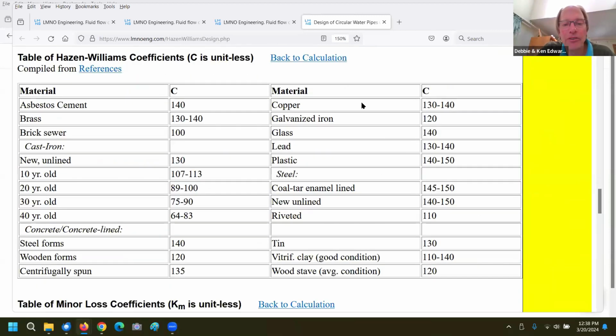Come down here, for instance, copper pipe, your C coefficient's like 130 to 140. Galvanized iron's a little lower. Lower number means rougher. Plastic, 140 to 150, pretty smooth. These are for materials that are newly put in a system. Over time, especially in the water industry, you're going to get calcium and magnesium and other multivalent ions plated out on the inside of the pipe. So your pipe will actually get smaller in diameter over time, and will also have a different roughness, because you no longer have the water contacting the actual pipe material. You have it contacting those precipitated ions sitting on the inside of the pipe wall. And concrete is a little rougher, and so on.